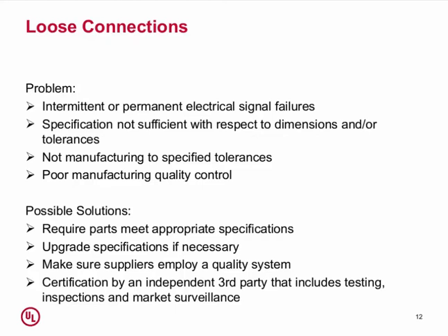Often, or it could be caused by the specification itself not being sufficient with respect to the actual dimensions or tolerances. What we've found or heard in the industry at this point is that, in general, a specification like TIA 1096 has real good specifications on the plug, but maybe a little bit wanting on the jack aspect of it. That could result in some loose connections.